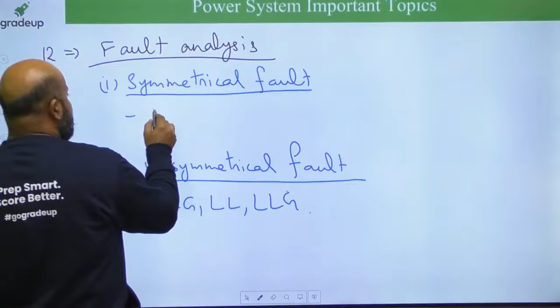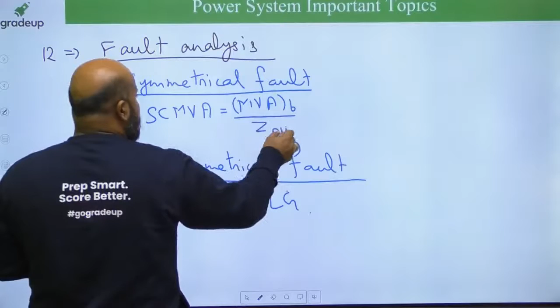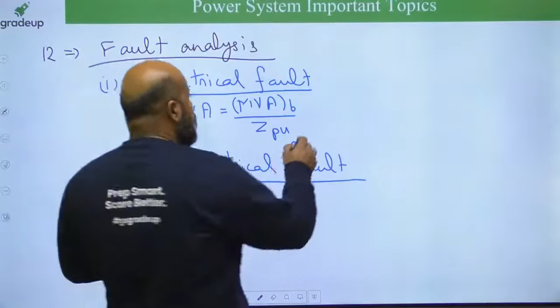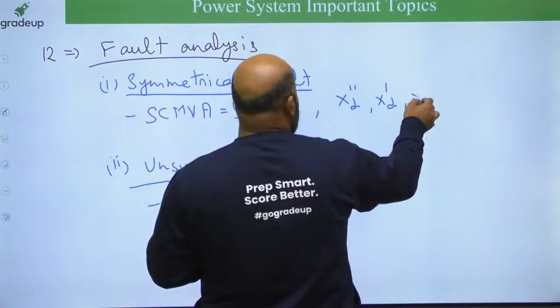Apart from that, in the symmetrical fault, you must read about the short circuit MVA rating. How to calculate that? You know it is equal to MVA base upon Z per unit - this is the formula. They are asking some questions from this.